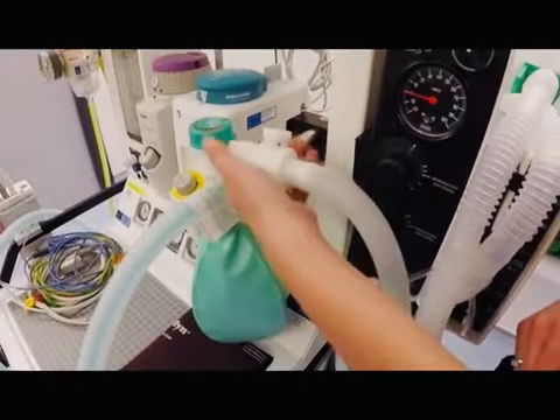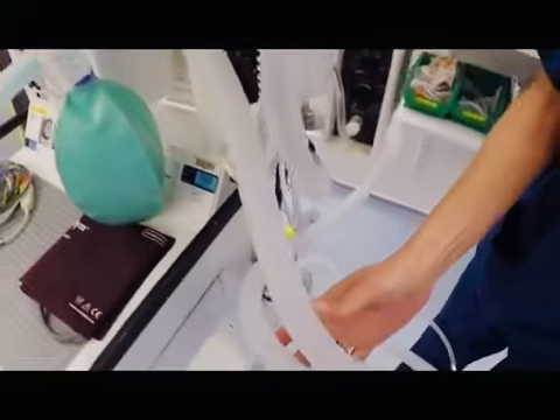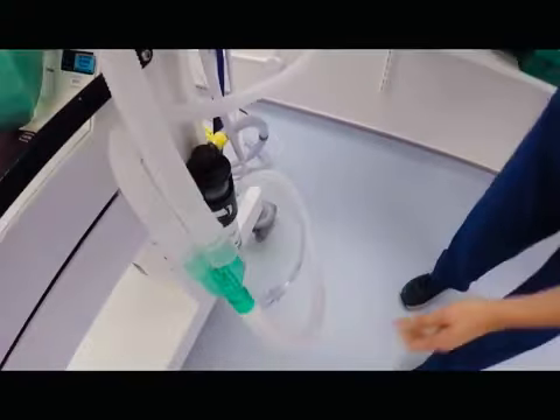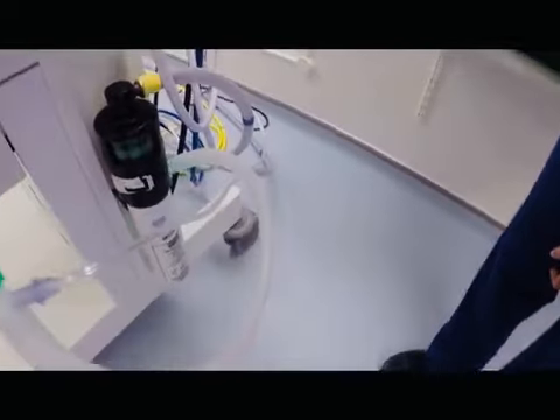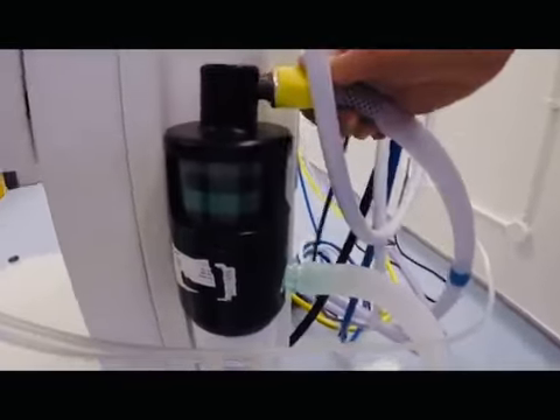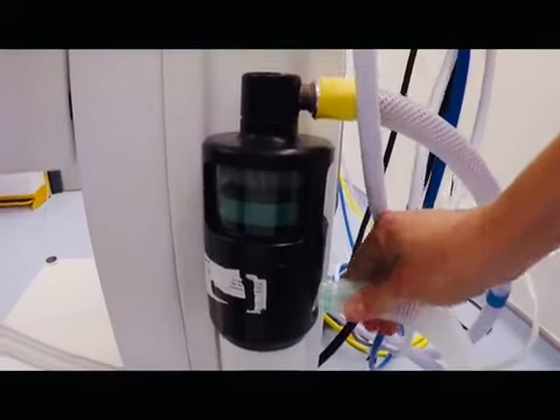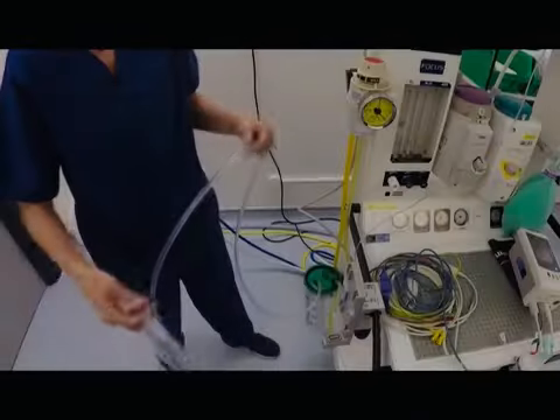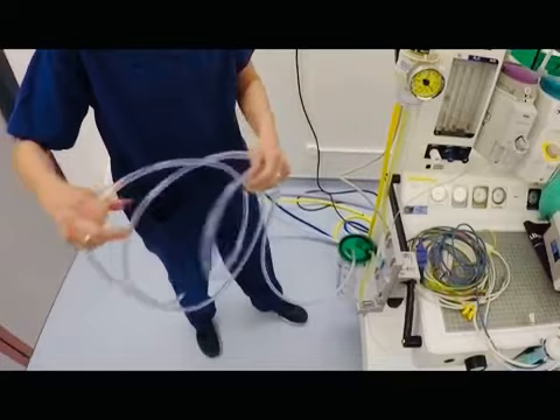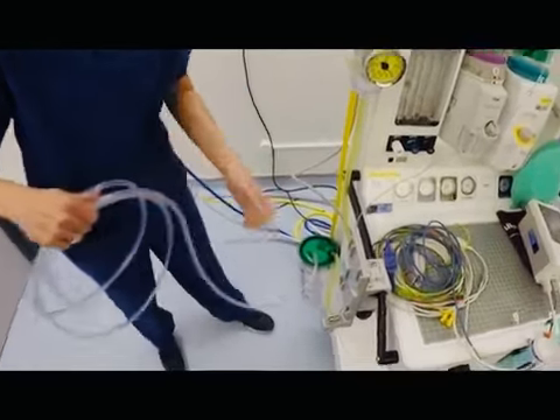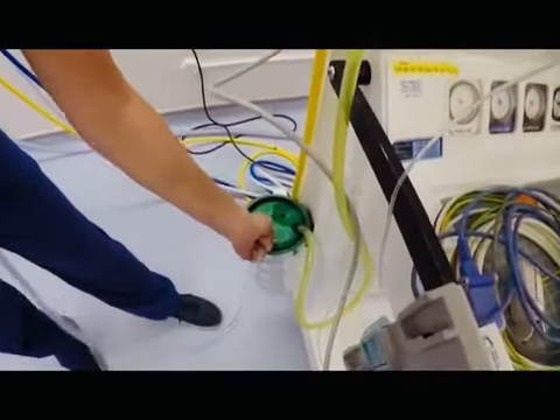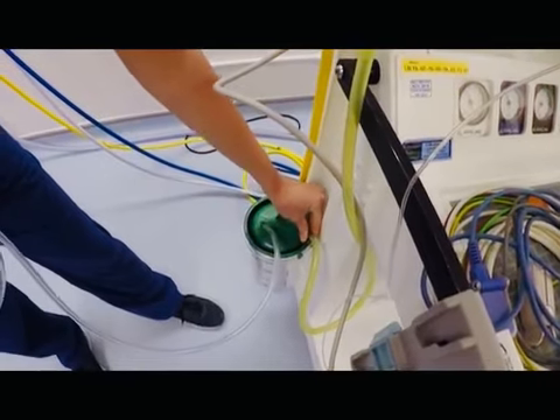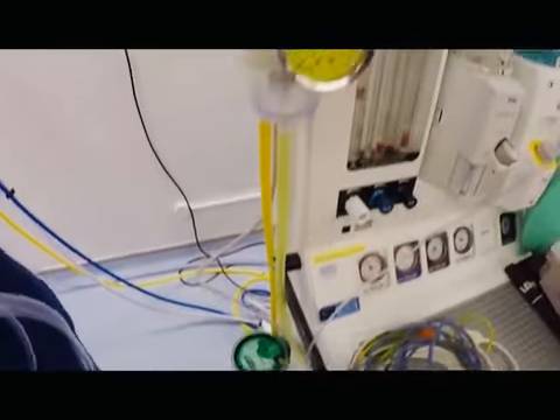Check the continuity of the scavenging assembly from the APL valve as well as the ventilator, if applicable, to the scavenging unit and then to the wall. The float should clearly be seen and an audible scavenging noise be present in the anaesthetic room. Check the suction tubing and attachments before switching it on and occluding the tubing. A negative pressure of -60 kPa should be reached to exclude a leak.